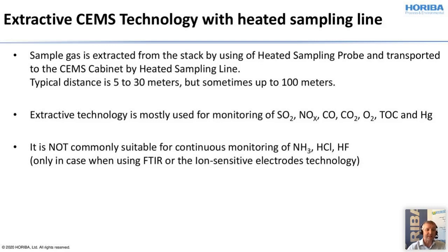When you remember back, we have a sample gas that needs to be extracted from the stack, and we use a heated sample line to transport the gas to the cabinet for the analyzer. Typical distance is between 5 to 30 meters, but sometimes it might be up to 100 meters, depending on the stack size and also depending on the location of the instrument in the cabinet. Extractive technology is mostly used for monitoring of SO2, NOx, CO, CO2, O2, but also total hydrocarbons and mercury. It's not commonly used for continuous monitoring of ammonia, hydrogen chloride, and hydrogen fluoride. This is only possible when an FTIR or ion sensitive technology is used.